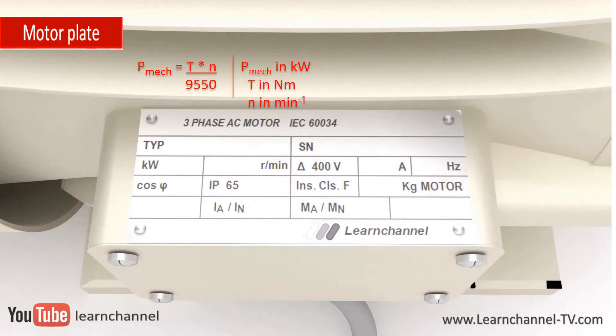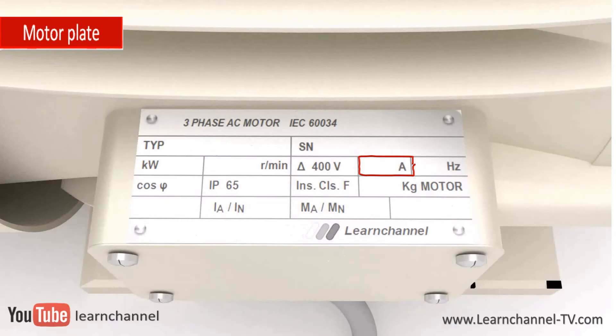The motor rated current is the amount of amperage in the power lines the motor needs when it is operated at full-load torque and mechanical output power. The motor operates with best efficiency when driven at the rated frequency for which it is designed. Europe and India have 50 Hz; America and Asia usually have 60 Hz.